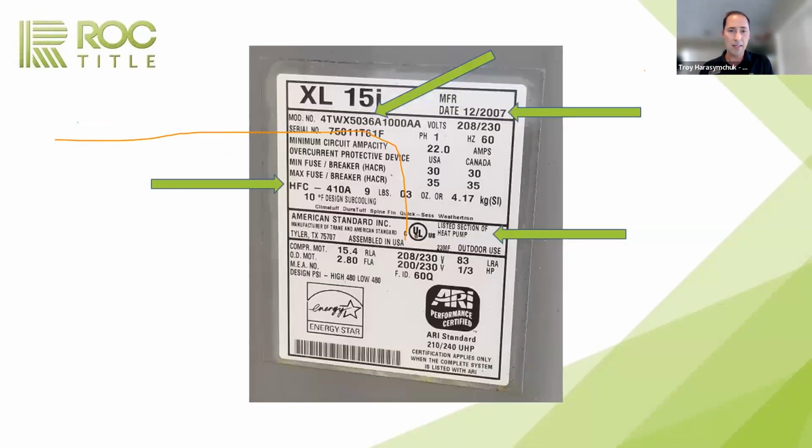So let's go ahead and see another label. This is American Standard, which is Trane. You're going to see here the manufacturer's date, 2007. So that was a split over a year, 2006, 2007. It could have R22, could have 410A. And sure enough, this one here is one of the first years they came out with 410A, because we can see that there. Heat pump, same thing.